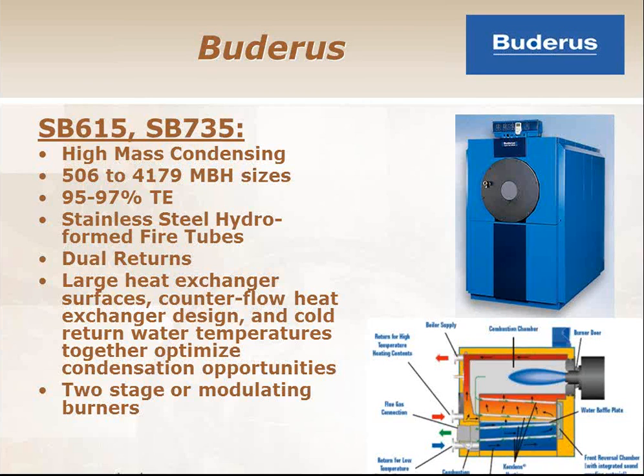They are stainless steel fire tubes. So fire tube means the flame is in the tube, like this drawing down here is showing you, and water is surrounding the tubes, right? So that's kind of the difference there. Water tube means the water's inside the tubes of the heat exchanger and the flame is blowing past the tubes. But because the water is surrounding it, there's a larger mass of water, hence the high mass boiler name, and hence not having the need for the primary, secondary to reduce the short cycling and things like that.